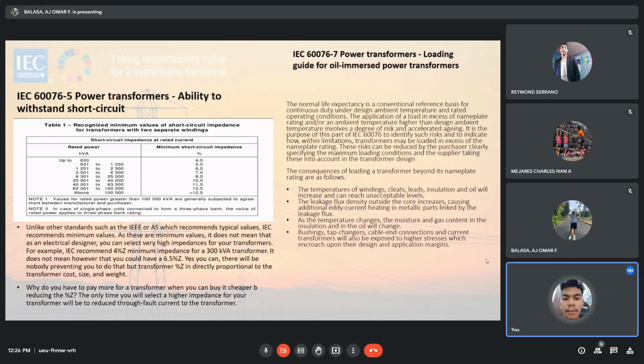Dito is yung normal life expectancy is a conventional reference basis for continuous duty under design ambient temperature and rated operating conditions. The application of a load in excess of nameplate rating and or an ambient temperature higher than design and ambient temperature involves a degree of risk and accelerated aging. Mas mabilis siya masira. It is the purpose of this part, IEC 60076-7, to identify such risk and to indicate how, within limitations, transformers may be loaded in excess of the nameplate rating. So, mababanggit yan mamaya, yung nameplate rating.